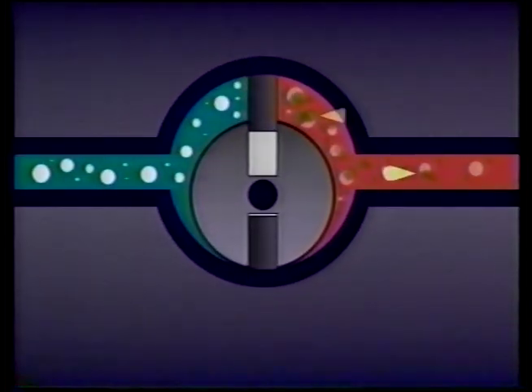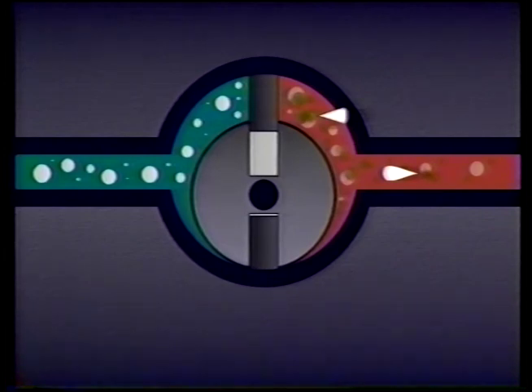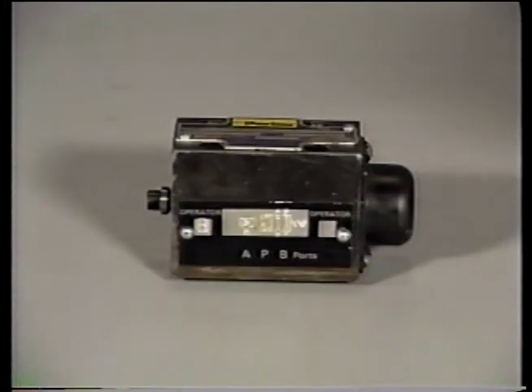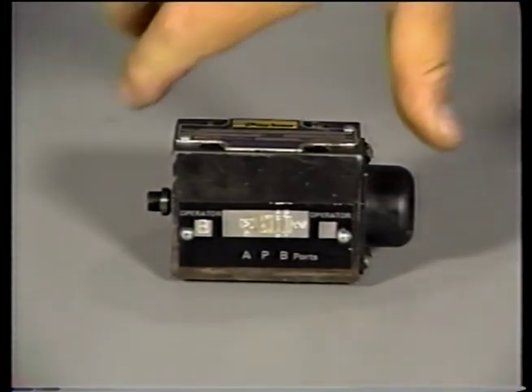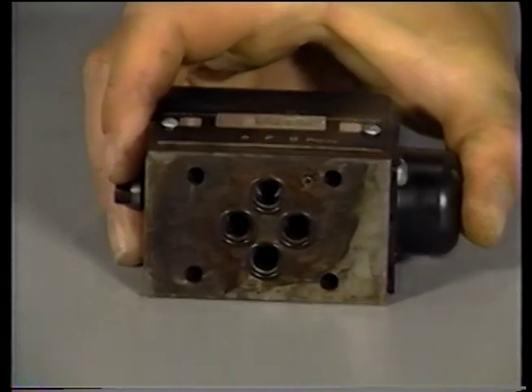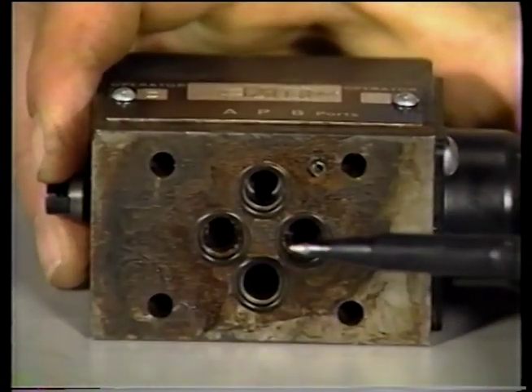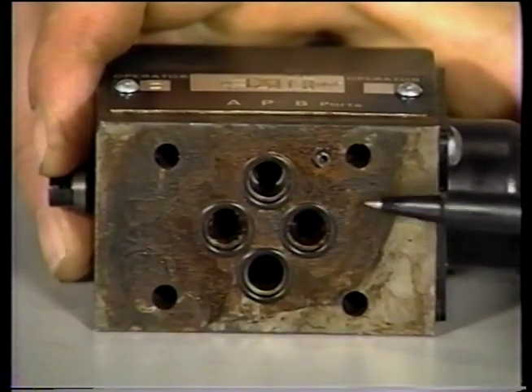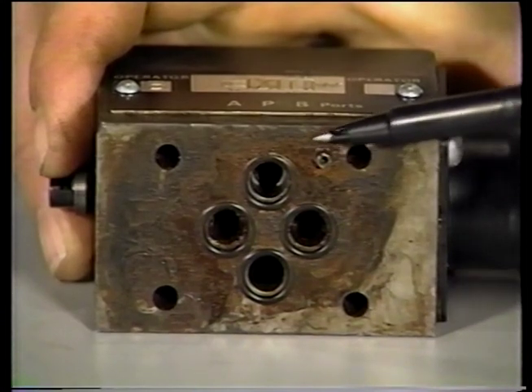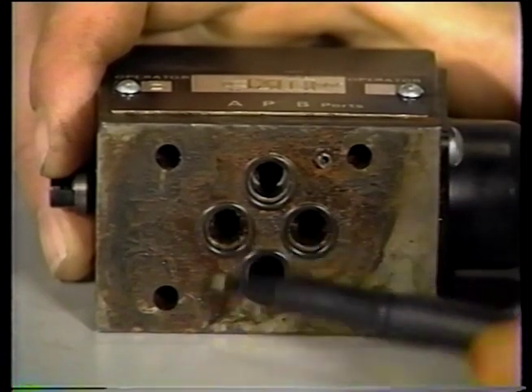forming resinous materials. The resins remain dissolved until they reach a hot metal surface, like a pump rotor or a valve. The hot surface will cause the resin to form a varnish that coats the metal surface. This varnish makes moving parts stick. The resinous material also forms a sludge that can plug up orifices and filters.